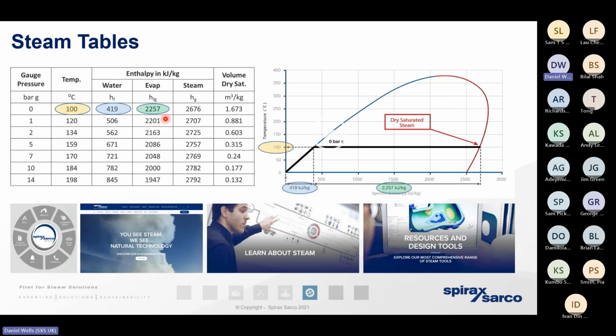So if I had my way, I'd draw a line through the enthalpy of evaporation, and I'd simply call it the useful heat energy. So when we take the useful heat energy away from the total heat energy, the energy that remains in that liquid condensate is exactly the same as the energy that appears in this column. So it really demonstrates the value of getting as much of that condensate back to the boiler house as we possibly can. That hot water is going to give us a really, really good head start in producing steam efficiently.